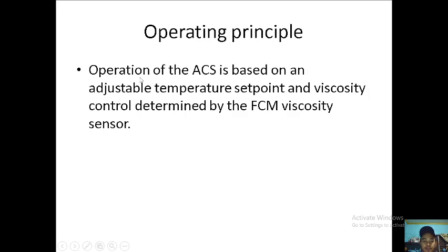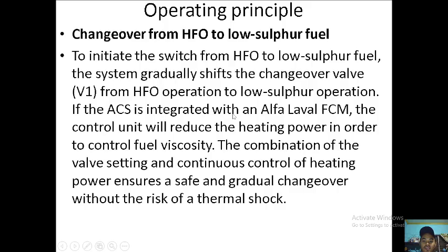Okay, operating principles. Operation of the ACS is based on an adjustable temperature set point and viscosity control determined by the FCM viscosity sensor. So, changeover from HFO to low sulfur fuel. To initiate the switch from HFO to low sulfur fuel, the system gradually shifts the changeover valve from HFO operation to low sulfur operation.